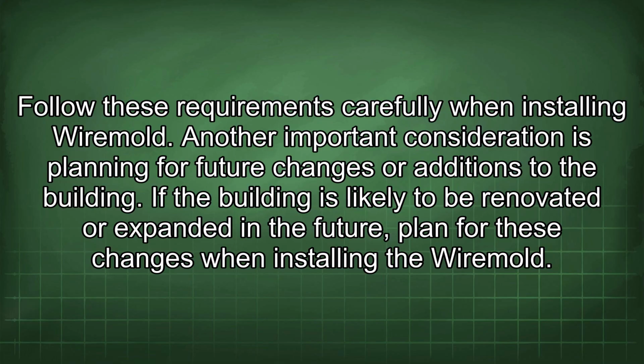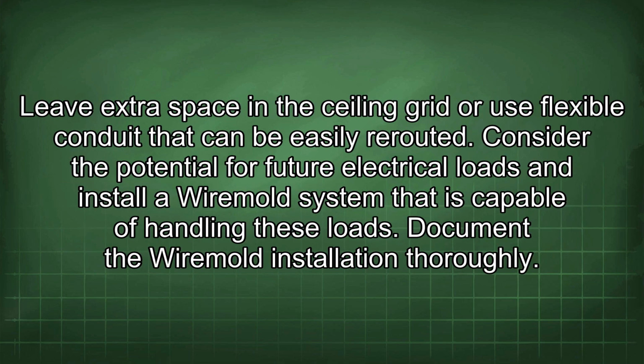Another important consideration is planning for future changes or additions to the building. If the building is likely to be renovated or expanded in the future, plan for these changes when installing the Wiremold. Leave extra space in the ceiling grid or use flexible conduit that can be easily rerouted. Consider the potential for future electrical loads and install a Wiremold system that is capable of handling these loads.